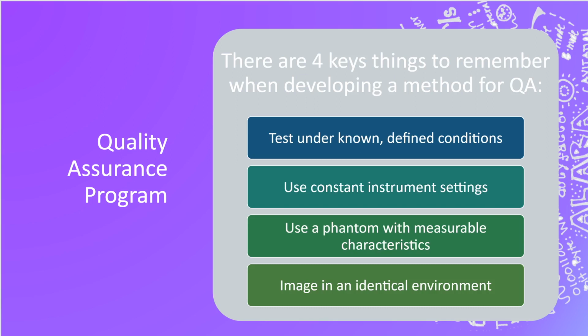And then lastly, we want to image in an identical environment. If you could set everything up, ideally it would be the same temperature, the same time, the same humidity, everything. That's not always realistic, but you don't want to move the machine into a really bright room where maybe you have to adjust some settings so you can see a little bit better compared to a really dark room. So you should always be having the lights at the same level. Try having the same person doing it each time so they can see those changes as they are going through the quality assurance checklist.